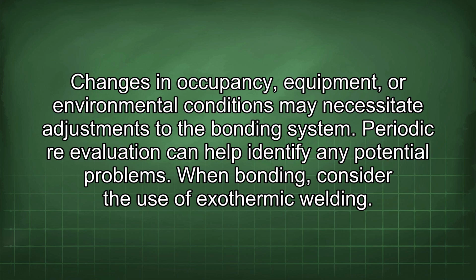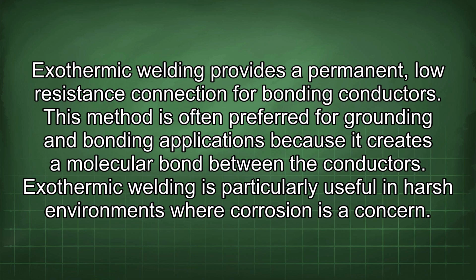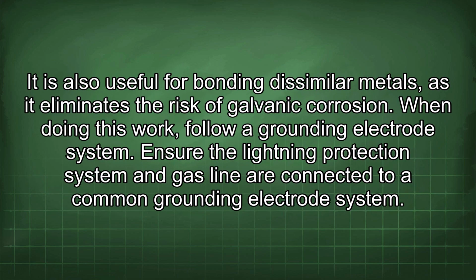When bonding, consider the use of exothermic welding. Exothermic welding provides a permanent, low-resistance connection for bonding conductors. This method is often preferred for grounding and bonding applications because it creates a molecular bond between the conductors. Exothermic welding is particularly useful in harsh environments where corrosion is a concern. It is also useful for bonding dissimilar metals as it eliminates the risk of galvanic corrosion.